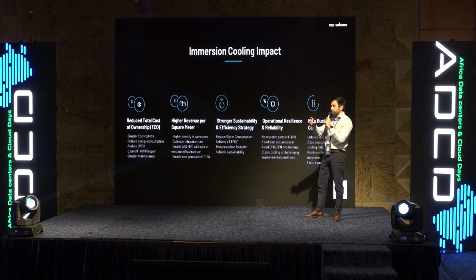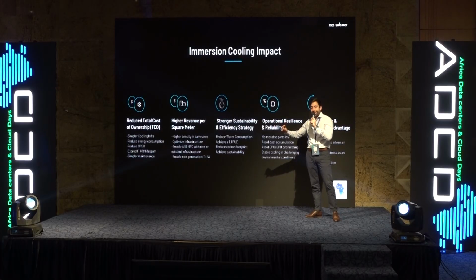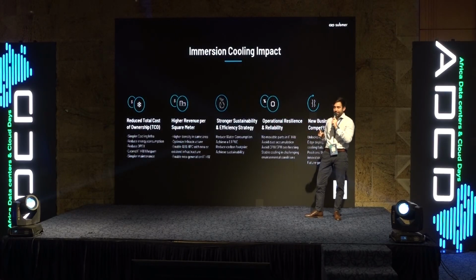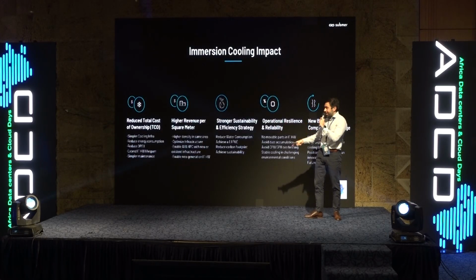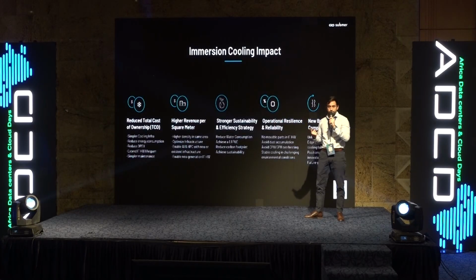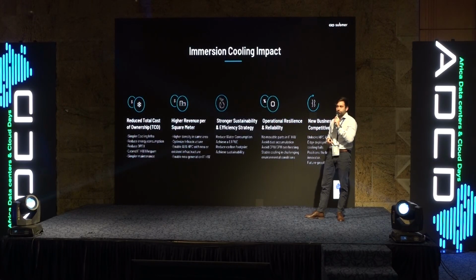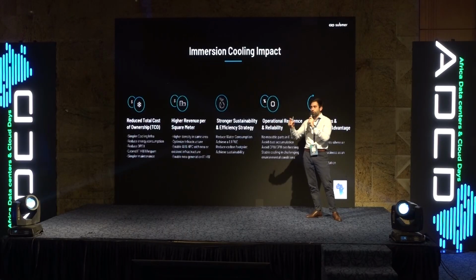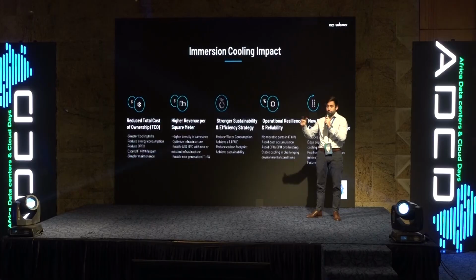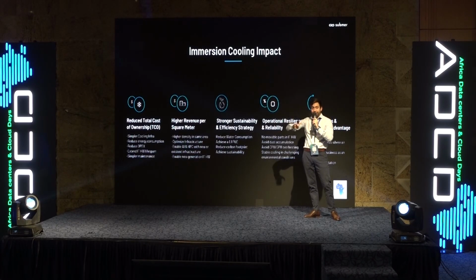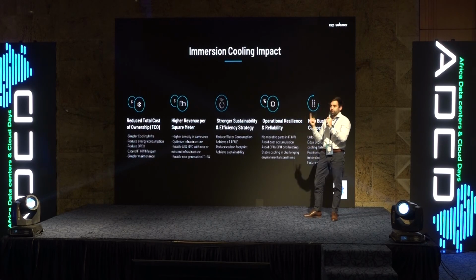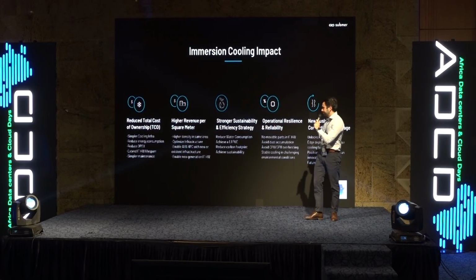If you compare it to DLC, direct-to-chip or direct liquid cooling, you have 2 water circuits going to the data center and to the data hall. In the case of immersion cooling, you just have one water loop. In Barcelona, we have the Barcelona Supercomputing Center, an HPC node, and they are using 3 water loops for the racks: one for DLC, one for the rear door heat exchangers, and another for comfort cooling. So in the end, you have 3 different water loops, which increases the CapEx when you're constructing the data center.